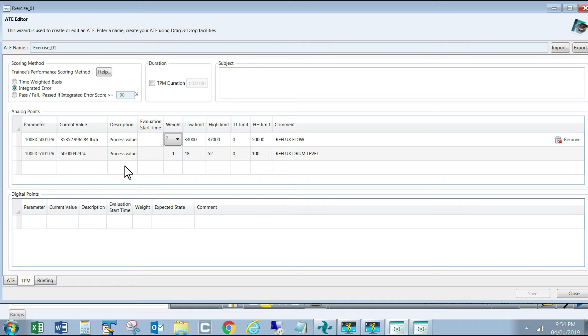I'm also giving a weight — whenever these variables are outside their limit, what's the penalty, how heavily should the operator be penalized? For example, reflux flow is more important, so it carries a weight of 2. The level is not so important, so it has a weight of 1. You can basically have a weight anywhere between 1 and 10, 10 being the highest penalty and 1 being the lowest. You can program as many variables as you want for any exercise.